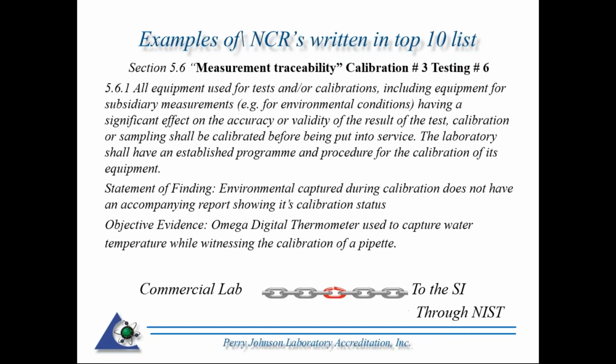Top of the list in both calibration and testing is section 5.6, which is measurement traceability. A little depiction at the bottom there is talking about traceability. That is traceability to the SI through NIST. Again, we have a policy guide in regards to traceability. I believe we're going to touch on that here in a little bit, with examples of nonconformances that were written against the policy guide.